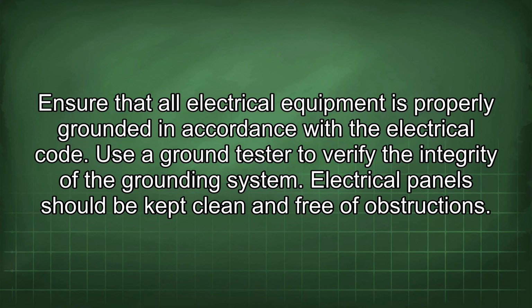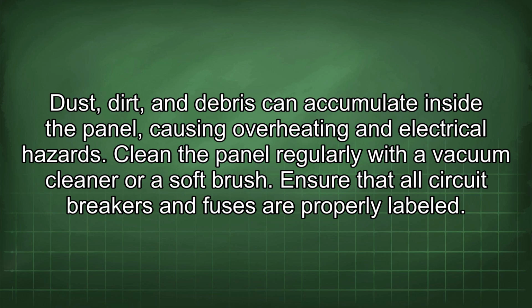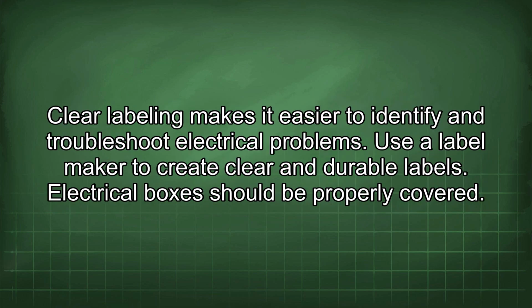Electrical panels should be kept clean and free of obstructions. Dust, dirt, and debris can accumulate inside the panel, causing overheating and electrical hazards. Clean the panel regularly with a vacuum cleaner or a soft brush. Ensure that all circuit breakers and fuses are properly labeled. Clear labeling makes it easier to identify and troubleshoot electrical problems. Use a label maker to create clear and durable labels.